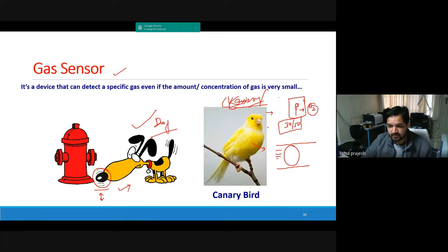So you have resistive gas sensors, then you have capacitive gas sensors, acoustic gas sensors, and optical gas sensors. So what we do in these technologies? If you talk about the first technology, which is resistive gas sensor, you are actually trying to measure the change in resistance of a particular material. As soon as there is gas on the surface, the resistance of this particular material will change, and with the help of electrodes, you will be able to measure it. Then you have capacitive gas sensors. In capacitive gas sensor, you actually measure the change in capacitance. Now, the change in capacitance might be directly due to material thickness change. Sometimes these materials have swelling effect, so the gap between electrodes will change, or the dielectric constant of the material is changing. Okay, so that will in turn change the capacitance of the material.